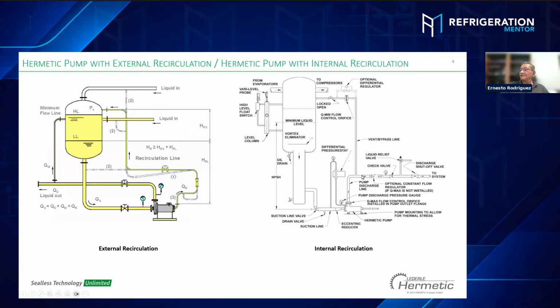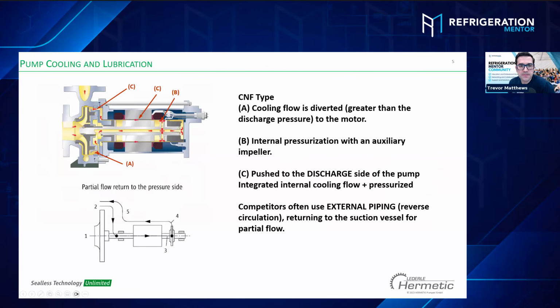I want to explain how the operation differs within the system. In the external circulation system, you can see we have the vessel and we have the piping. The external piping goes back to the vessel on the external part of the circulator. Now, with internal circulation, we save all this piping. At some point, we have the standard pump installation with no extra piping. This is the typical installation for internal and external recirculation. Okay, how to operate the flow?